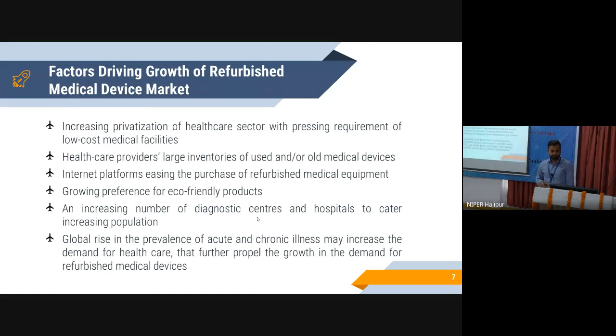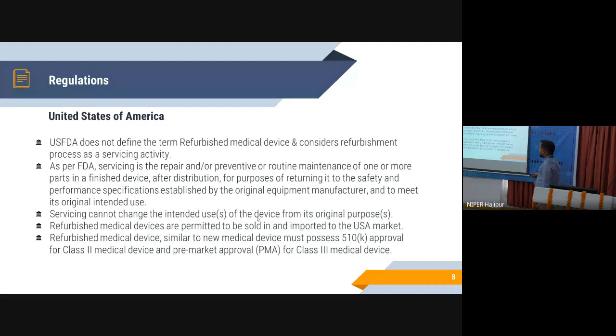Now we will discuss the current regulations being practiced across the globe. I'll start with the US FDA. The US FDA doesn't define the term refurbishment or refurbished medical device. The US FDA considers refurbishment a servicing activity. As per the FDA, servicing is the repair and/or preventive or routine maintenance of one or more parts in a finished device, an old device or a used device once it is distributed, for the purpose of returning it to the safety and performance specification established by the original equipment manufacturer and to meet its original intended use. One thing I need to mention here is that refurbishment doesn't alter the intended use of the medical device.